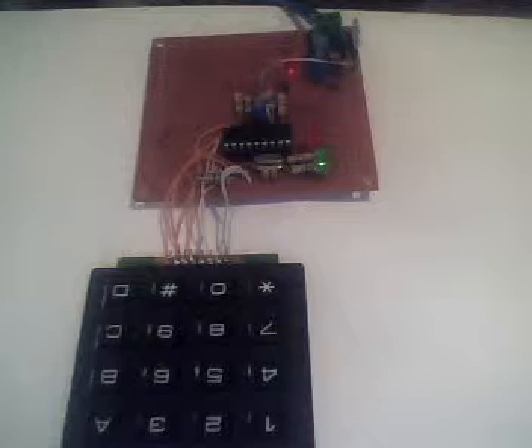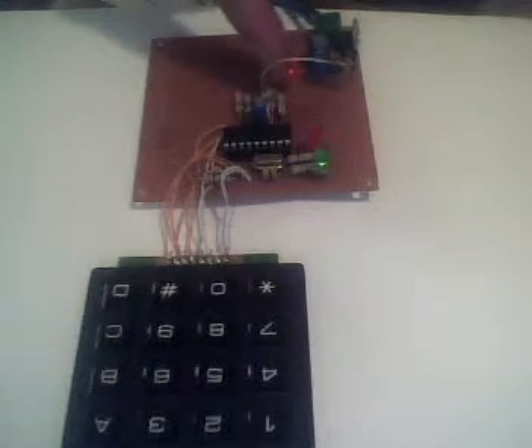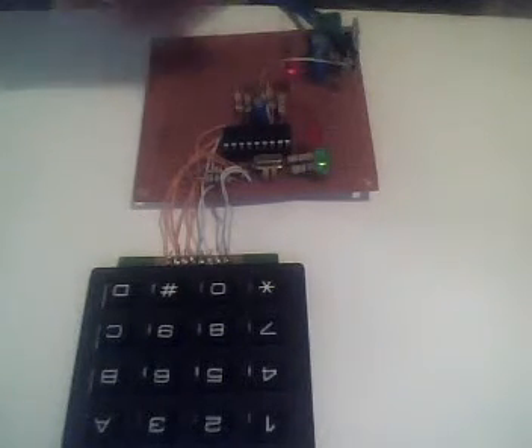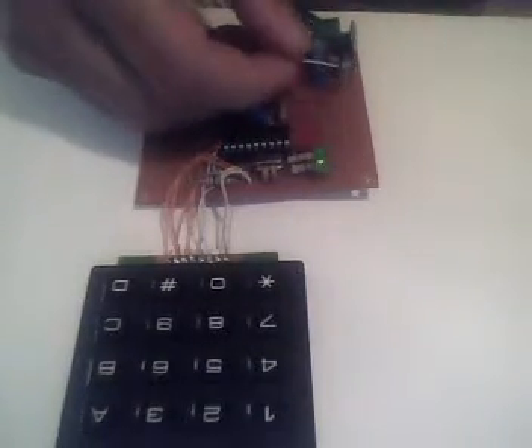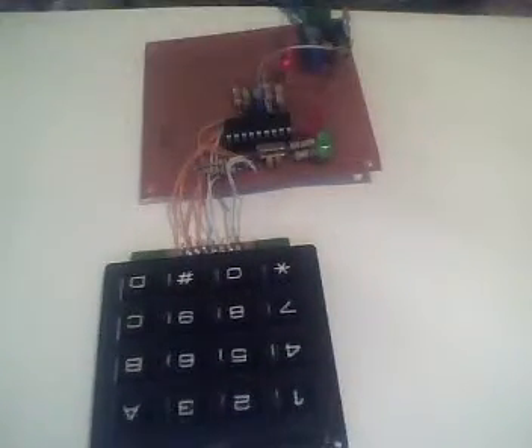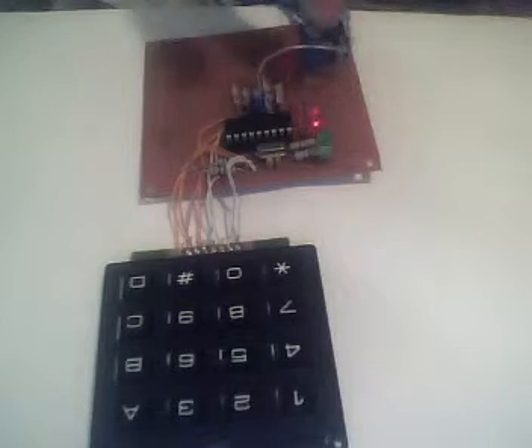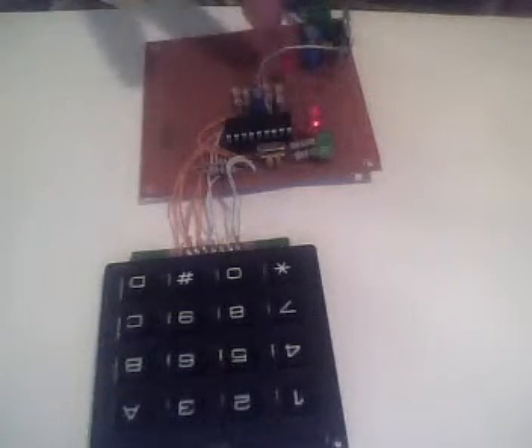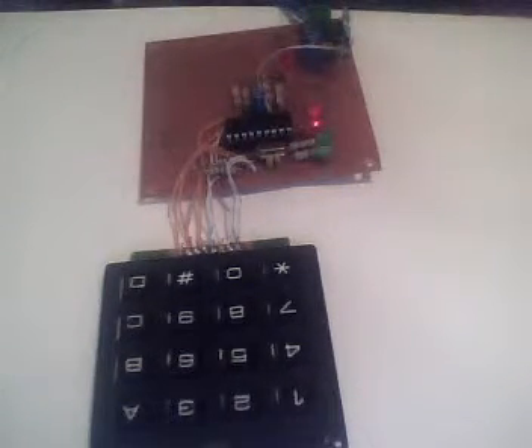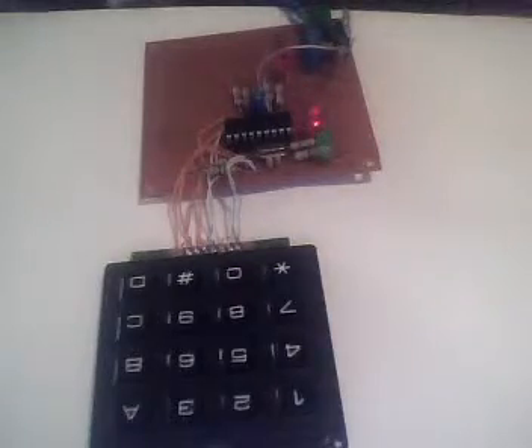156A is the code. The green LED is on. This red LED is on. The lock is open. The lock will not close until the door is closed. That means the limit switch is closed. After the limit switch closed, the system is neutral and the lock is closed.